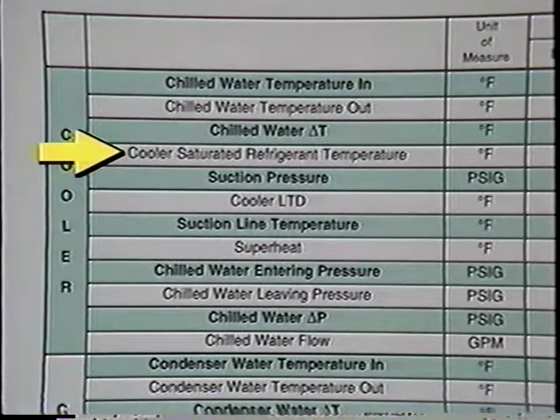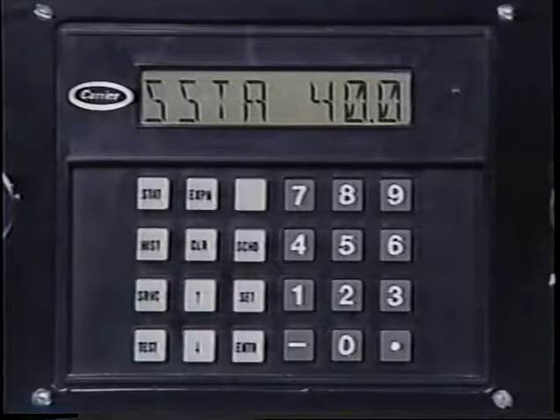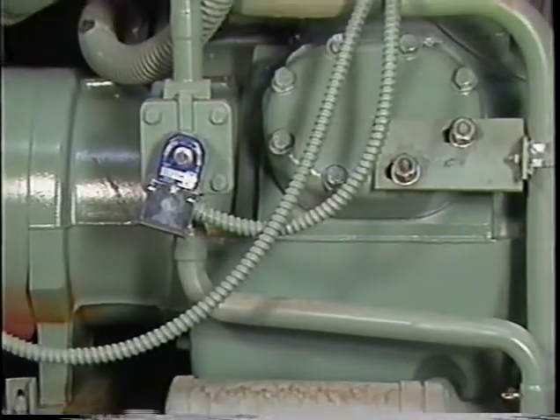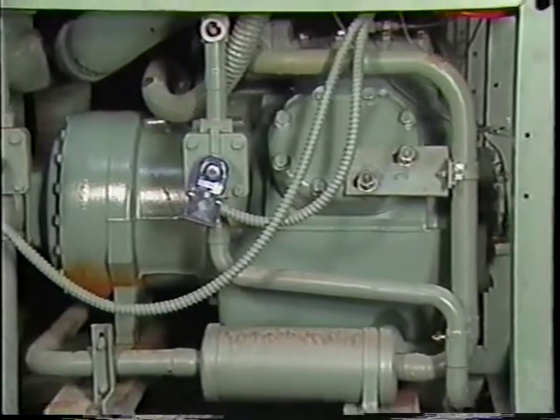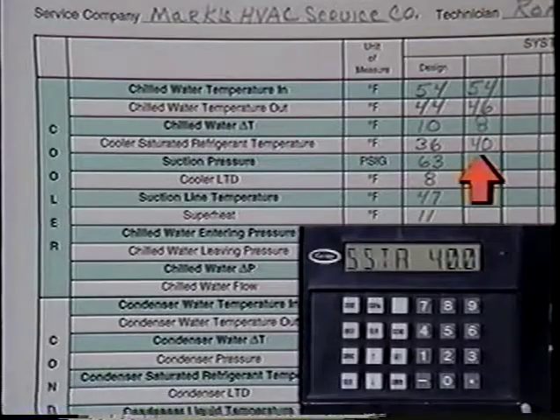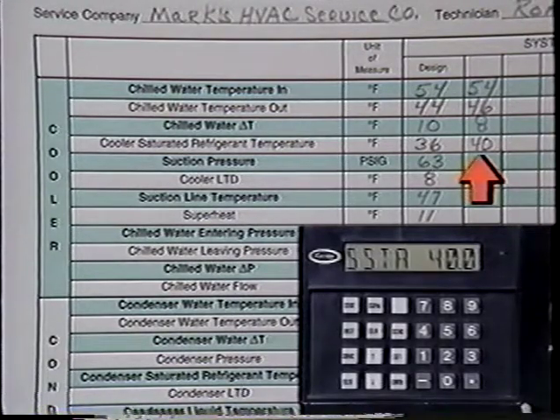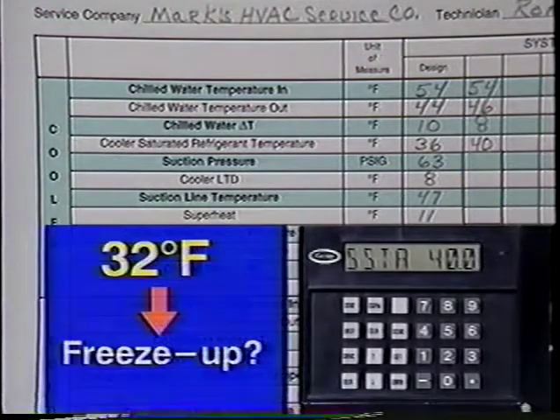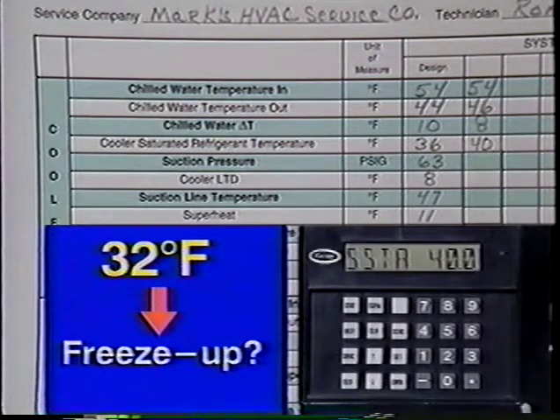Cooler saturated refrigerant temperature. A space is provided to record the cooler saturated refrigerant temperature. Under maximum heat load conditions, with the machine operating at design, this temperature should be at the design temperature. Under reduced heat load operation, when the compressor is running unloaded, this temperature will be above design. Under no circumstances, even at full load operation, should this temperature be allowed to drop below the design temperature, which is typically a few degrees above 32 degrees Fahrenheit. If the cooler saturated refrigerant temperature is at 32 degrees or lower, then the possibility of a freeze-up exists.